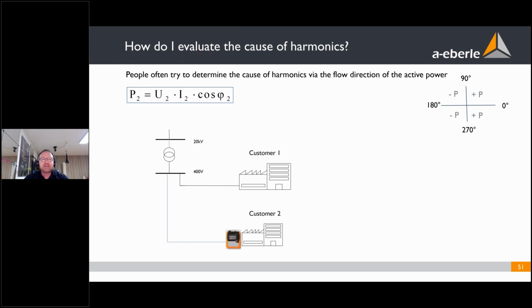Okay, the last 5 minutes I will invest to speak about how we can analyze with power quality analyzers who is responsible for the disturbances, who is responsible for the harmonics in your grid. And I see that people often try to analyze the direction of the real power of a harmonic. The direction of the power of the harmonic should tell you who's responsible, who's producing the harmonic. And I will tell you why this is wrong in 90% of the cases.